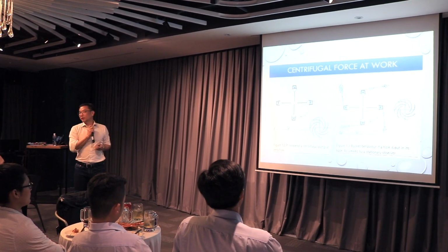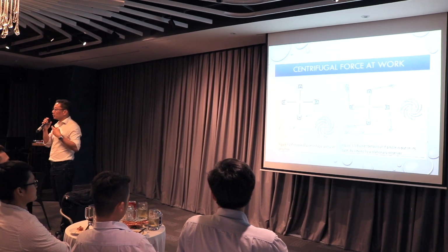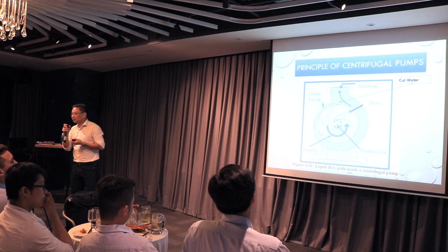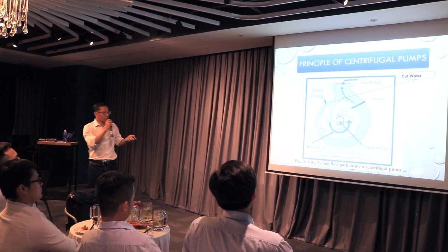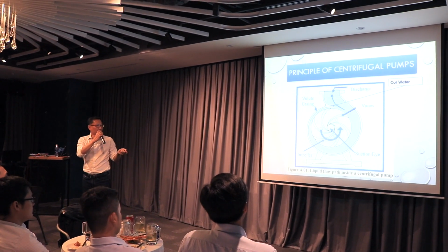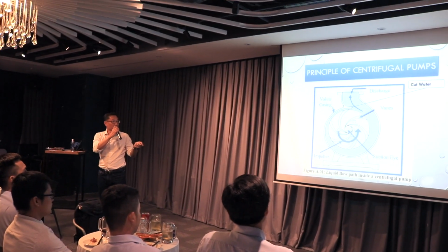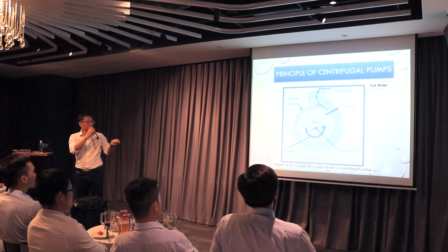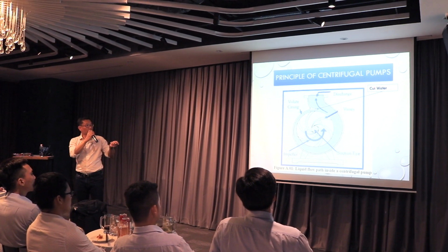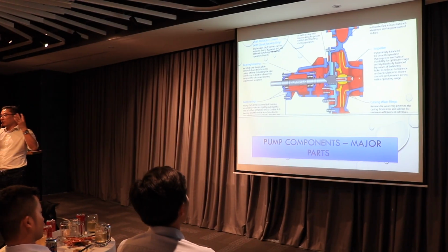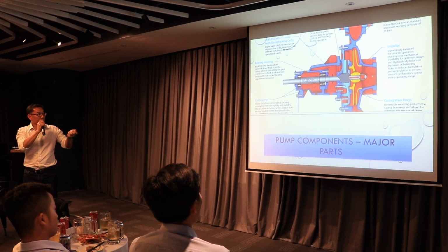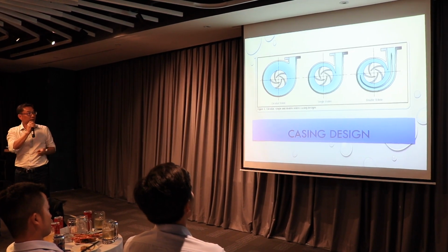There are many slides here, sorry, so I will not touch on them all, but more important is what we look at. Inside the pump, there are only a few components that are important. The impeller suction eye, the casing, the discharge, of course there's suction here, and then there's a cut water. The pump's efficiency depends on how efficient the hydraulics inside the casing are. This is the major part.